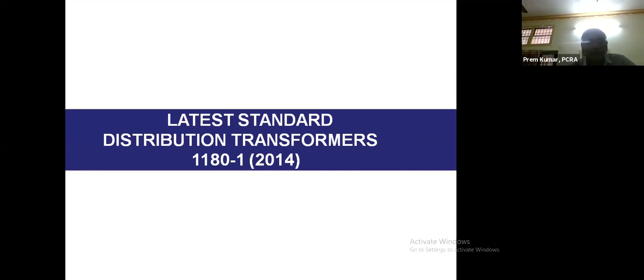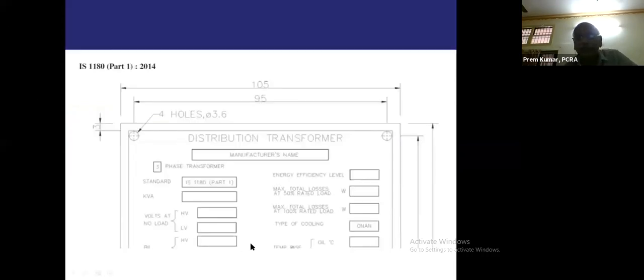Then slowly they phased out the level 1 transformers. Level 1 transformers are no longer available in the industry, no longer manufactured, and a consumer is compelled to go in for level 2 only. This is how the Government of India is slowly introducing the energy efficiency concept. Similarly, for motors, IE1 is no longer manufactured, only IE2 is the minimum. And sooner or later, IE2 will also get phased out, and one has to go in for super efficiency, I mean, IE3 motors only. And we'll have to see a case study. In a transformer, you have to see the standards here: what standard is being manufactured? So this is the standard.